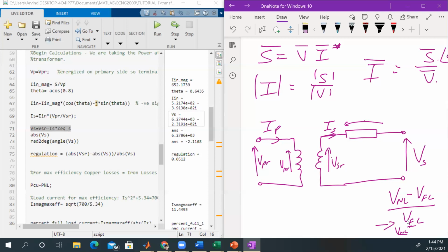If you look at the standards, usually when you think about a device, like when we come to motors, the power requirements and horsepower you are given would be on the output, because you want to know when you buy the machine whether it could move your load, not about all the losses. So you want the value on the motor spec to be the value it could move, so you could just say yes, this meets my requirements and I could get it. But that's because the motor is an end-use device.